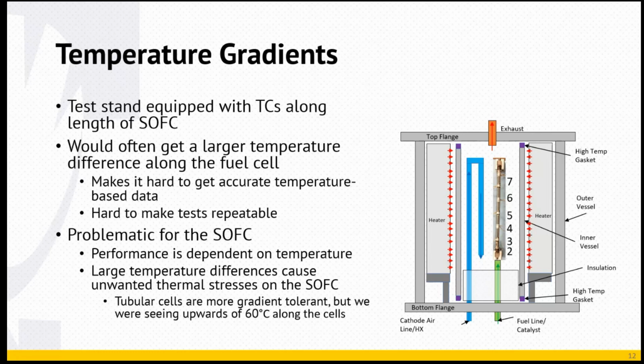Really the main driver for this was we just wanted better data, because it's hard to make comparison test runs at 750 and 700 degrees Celsius when your tube isn't at the same temperature all along it. It also made tests hard to repeat, because it depended on how long we let the test stand equalize its temperature. If you gave it 3 hours to warm up, it would be a smaller gradient, but if you only gave it an hour and a half, it would be a much larger gradient. So it was always a balance of how much time we had versus how equalized we let it get.